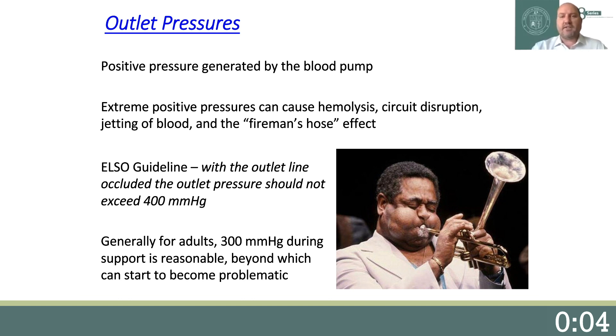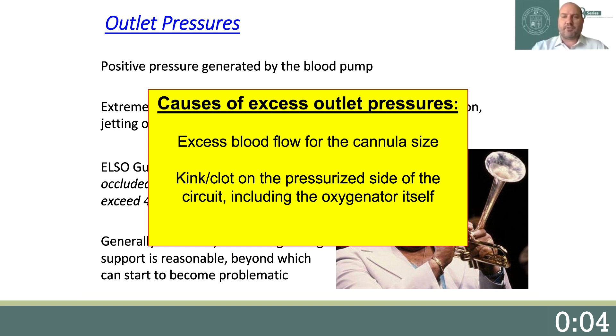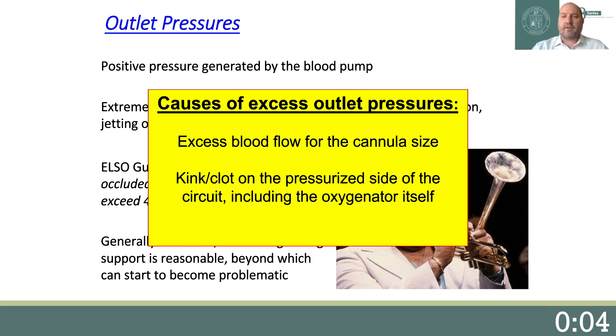Understanding the etiology of increased outflow pressure and how to resolve it is also critical. Causes of increased outflow pressure include excess blood flow for the cannula size, or a kink or clot on the pressurized side of the circuit, including the oxygenator itself.